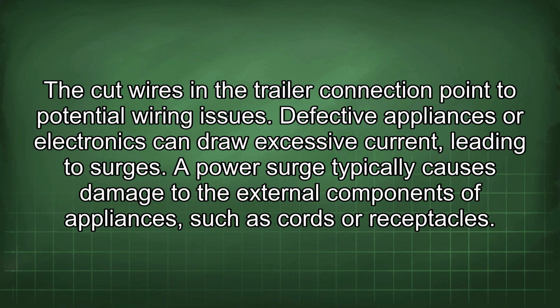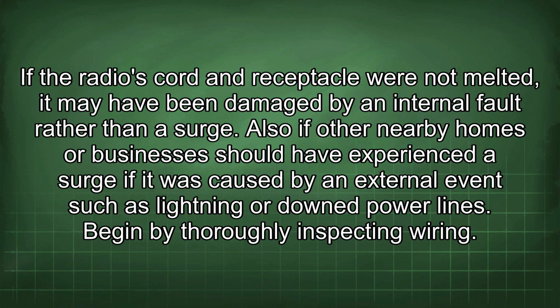Defective appliances or electronics can draw excessive current, leading to surges. A power surge typically causes damage to the external components of appliances, such as cords or receptacles. If the radio's cord and receptacle were not melted, it may have been damaged by an internal fault rather than a surge. Also, if it was caused by an external event such as lightning or downed power lines, other nearby homes or businesses should have experienced a surge.